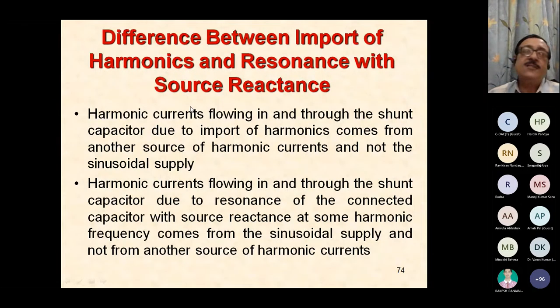In both cases, the source current harmonic increases. But in the case of import of harmonics, the harmonic currents are flowing in and through the shunt capacitor due to import coming from another source of harmonic currents and not the sinusoidal supply. Whereas in the case of harmonic currents flowing in through the shunt capacitor due to resonance, the source of the harmonic current frequency comes from the sinusoidal supply itself and not from another harmonic source. There is a distinction between the two, but the end results will be similar.